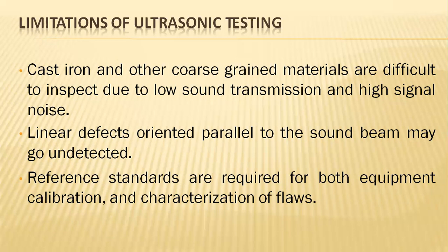Cast iron and other coarse-grained materials are very difficult to inspect because of low sound transmission and high signal noise occurring over it.